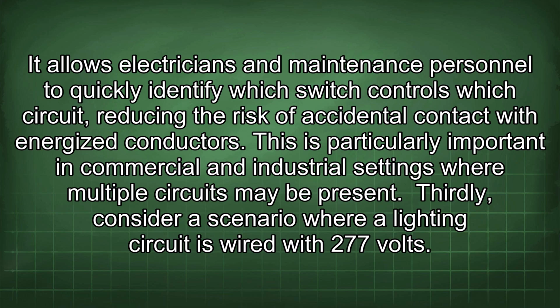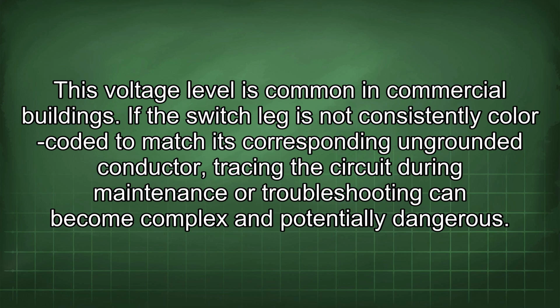Thirdly, consider a scenario where a lighting circuit is wired with 277 volts. This voltage level is common in commercial buildings. If the switch leg is not consistently color-coded to match its corresponding ungrounded conductor, tracing the circuit during maintenance or troubleshooting can become complex and potentially dangerous.